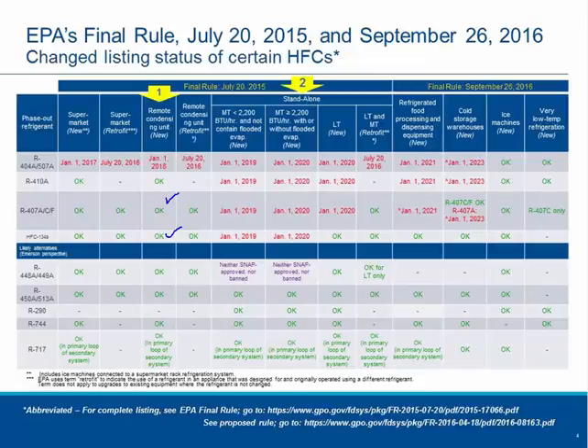So the alternative refrigerants that we have here are what's called R448A and 449A, as well as R450A and 513A. 448A is a 404A-like refrigerant that we have today. It's a medium back pressure refrigerant, and it's A1, non-flammable. We also have R450A and R513A, which are low back pressure refrigerants, great for medium temp applications. These numbers, 448 and 449A, are designated by the chemical manufacturers Honeywell and DuPont, the first being Honeywell, the second being DuPont, formerly DuPont, now called Chemours.